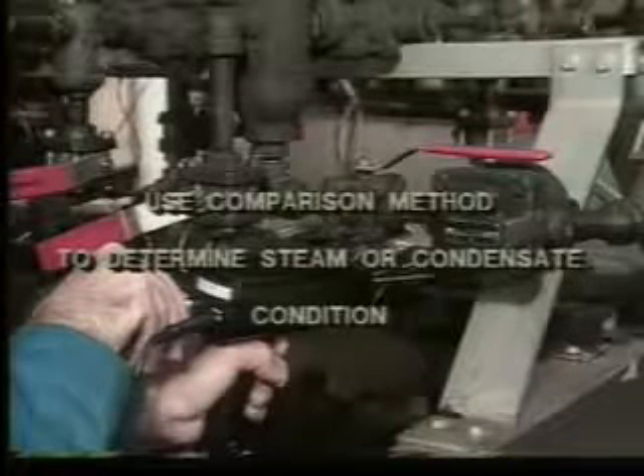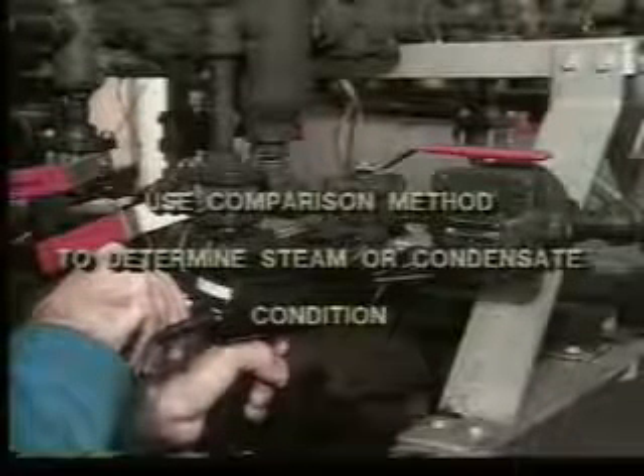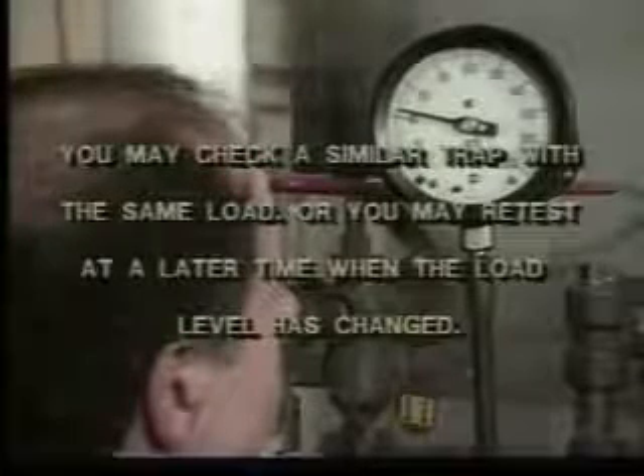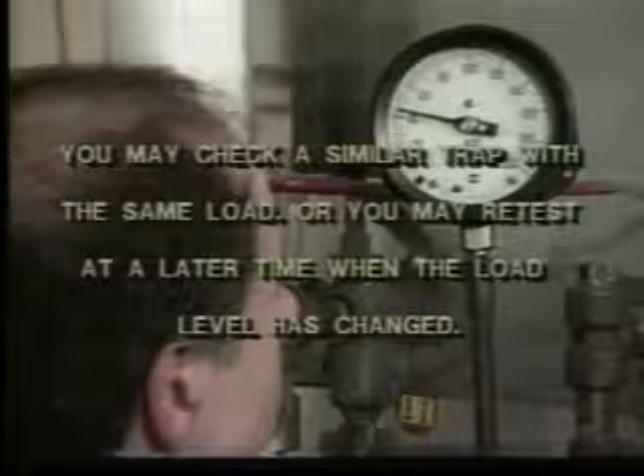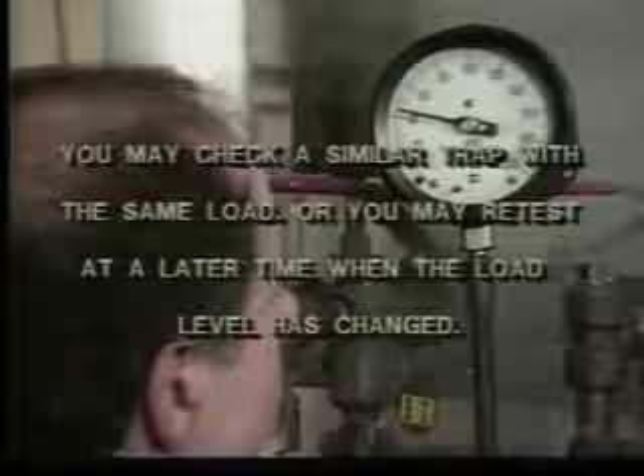If there is confusion in determining steam or a heavy condensate condition, use the comparison method previously described, touching steam and condensate lines. You may also check a similar trap with the same load, or you may retest at a later time when the load level is changed. It is important in testing this trap to know the condensate load of your system.